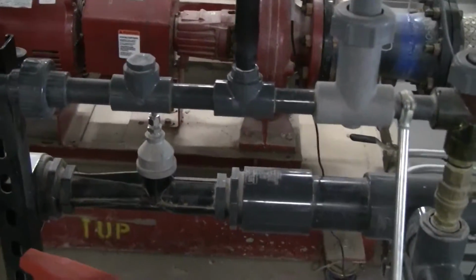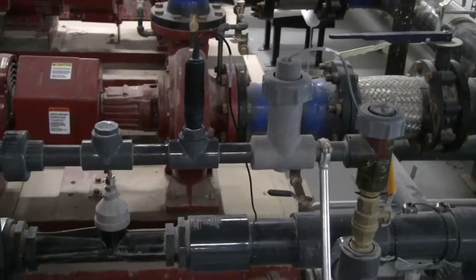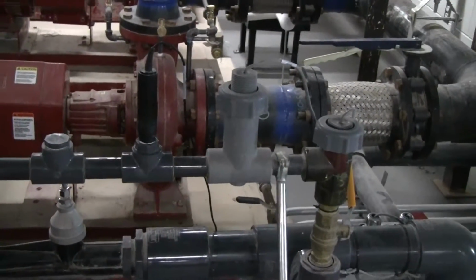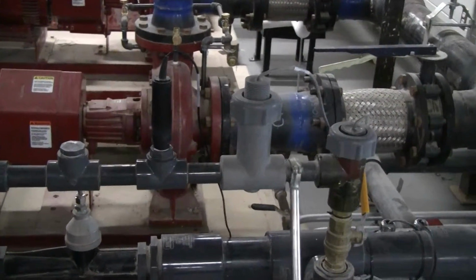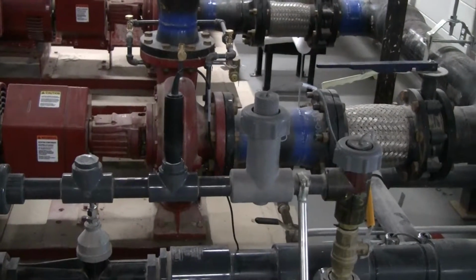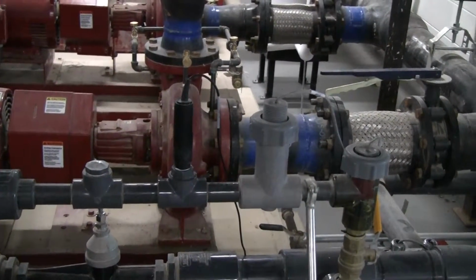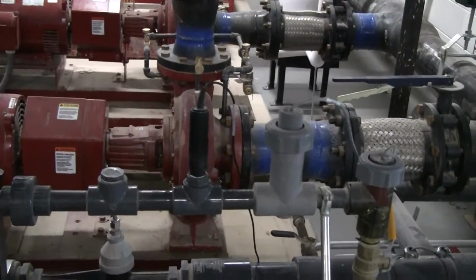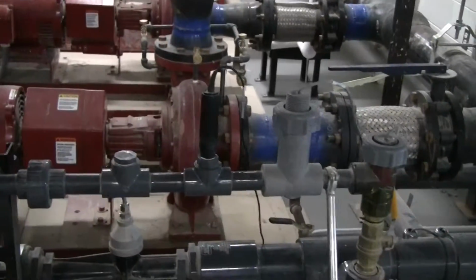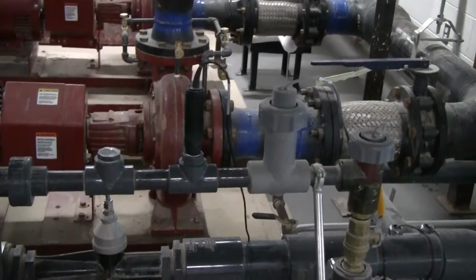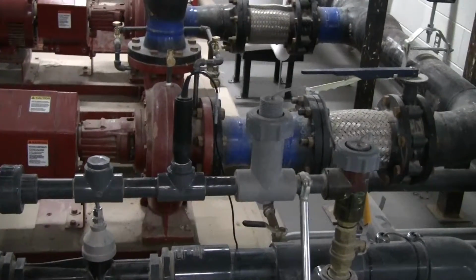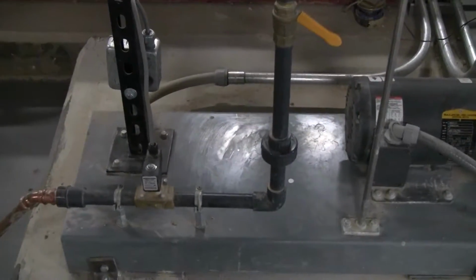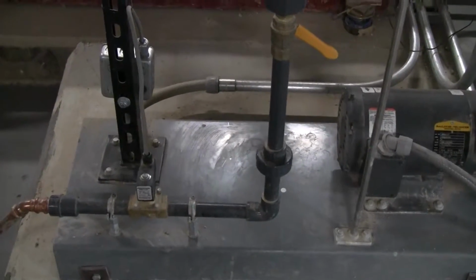This is the sample loop where we have the flow switch in case we lose the pump. It shuts the entire system down, so that's a safety feature where no ozone will be produced. We have the conductivity probe. That's reading the solids in the water to make sure we're maintaining proper cycles of concentration. As the solids in the water get too high, it turns on the bleed valve down here, discharging concentrated water so that fresh water is made up and we dilute the system down.